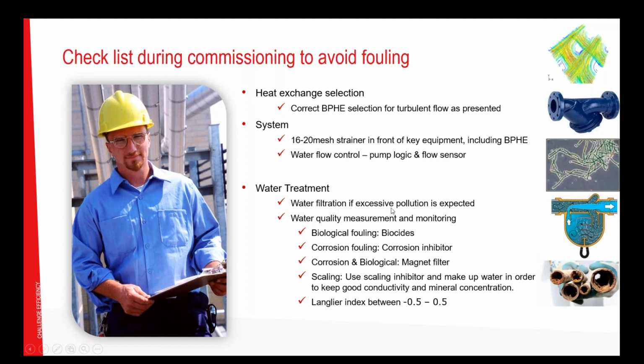Water filtration is important for open loop, because there is a continuous influx of small particles, and you don't want that to build up. So for open loop water systems, a filtration method to bleed out the small particles is recommended.